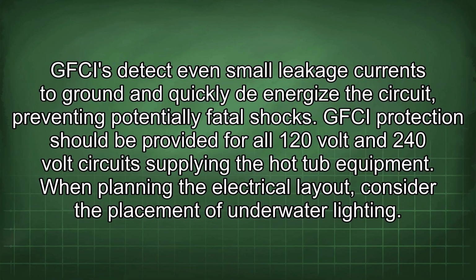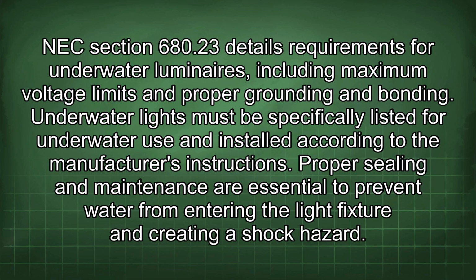GFCI protection should be provided for all 120-volt and 240-volt circuits supplying the hot tub equipment. When planning the electrical layout, consider the placement of underwater lighting. NEC Section 680.23 details requirements for underwater luminaires, including maximum voltage limits and proper grounding and bonding. Underwater lights must be specifically listed for underwater use and installed according to the manufacturer's instructions. Proper sealing and maintenance are essential to prevent water from entering the light fixture and creating a shock hazard.